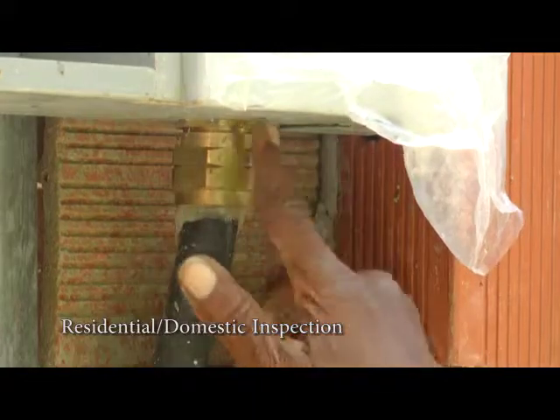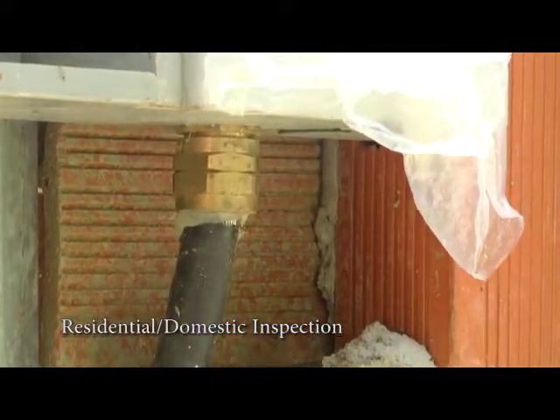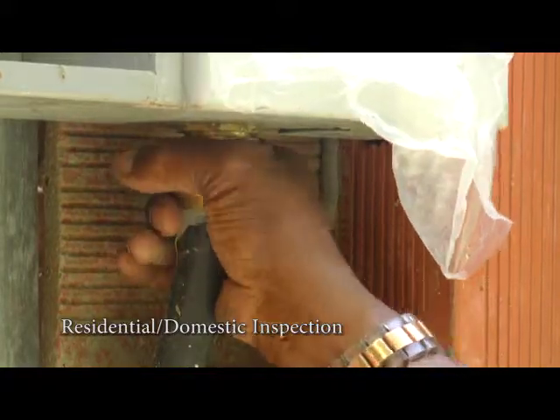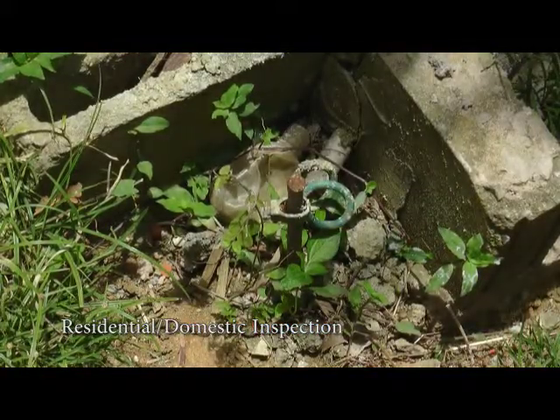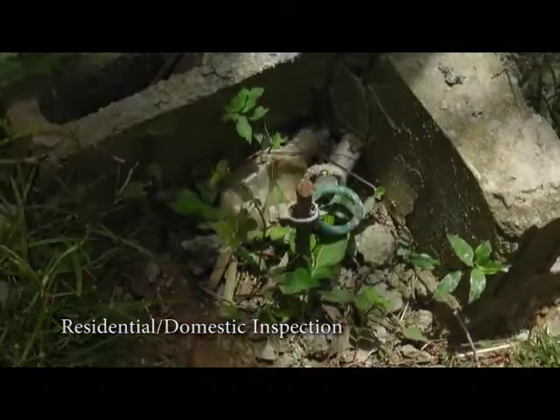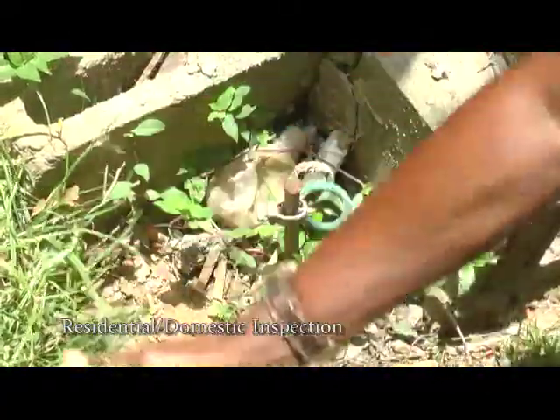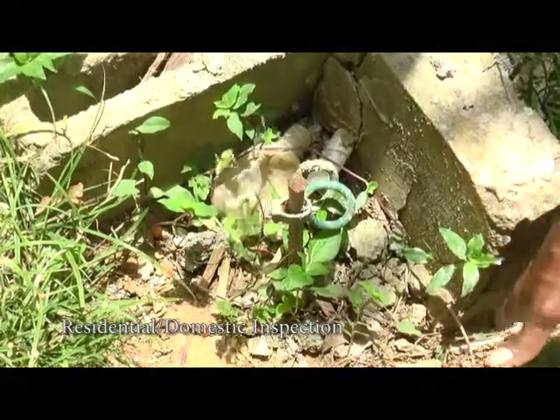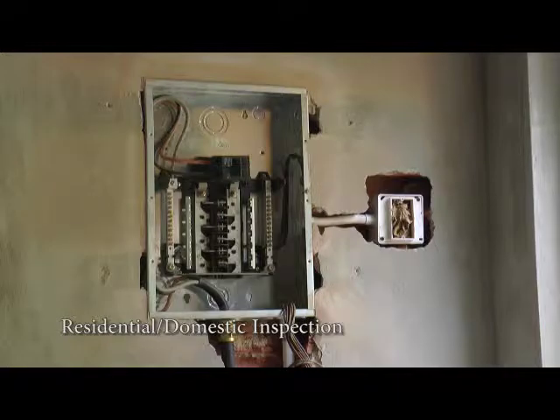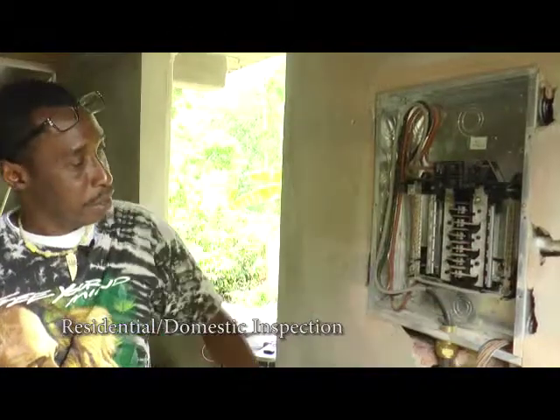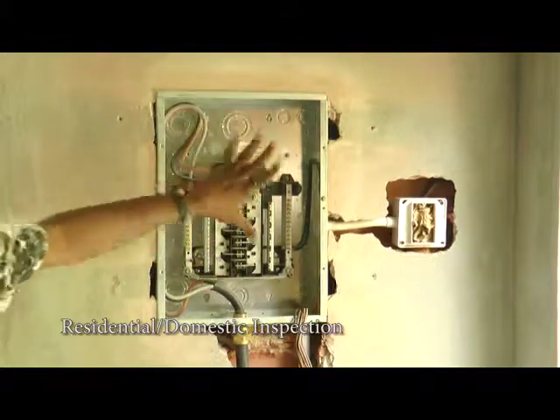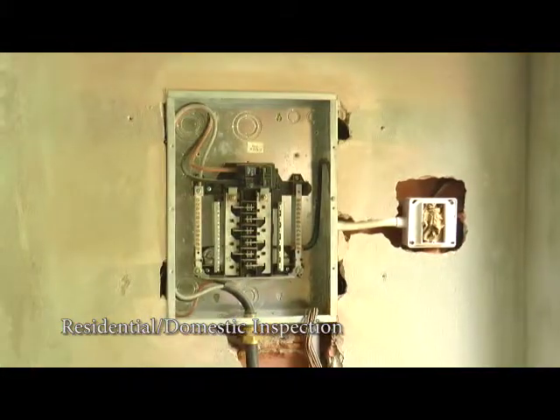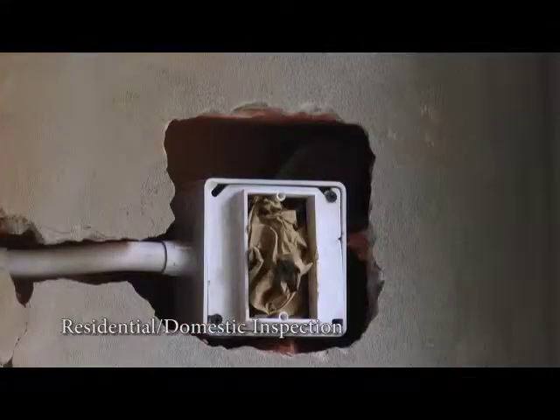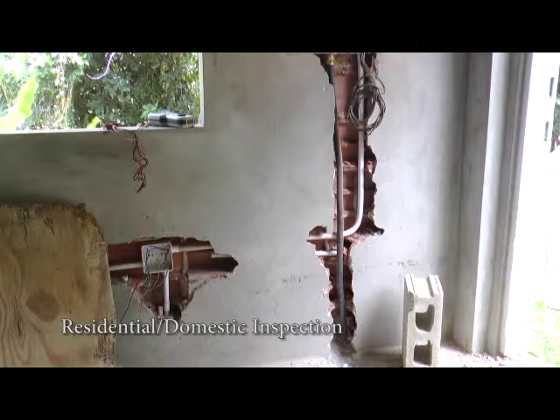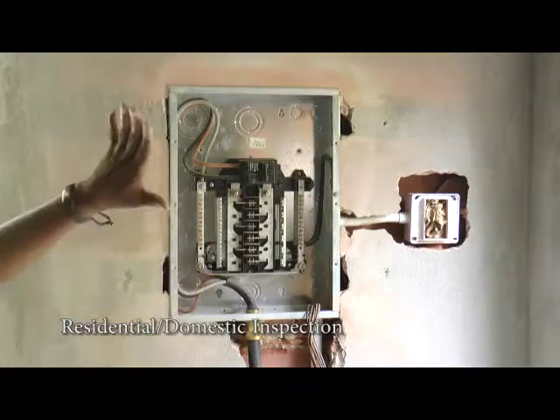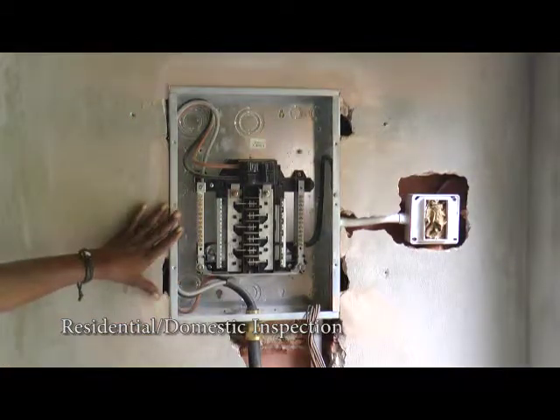This is the gland that connected here to the house, and it's slack, so the guy gotta fix this. This is broken. It's supposed to have this square to be protected. Right? It is tight and good here, but it needs to be protected by having this properly sealed. Final inspection where you have to have everything in place. All the breakers here and all the information on the installation of your whole installation, where every plug is, must be registered here. Right? But right now this is the mains only, and it's only valid for 3 months.